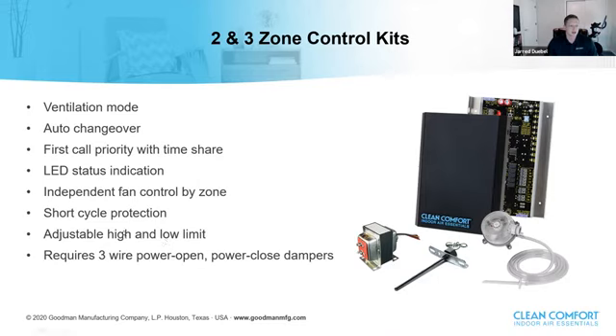Again, adjustable high and low limit. We talked about that as far as discharge air temperature is concerned. The high limit is adjustable between 130 and 160 degrees. The low limit is preset at 43 degrees. And lastly, it requires a 3-wire damper for the ESP series.